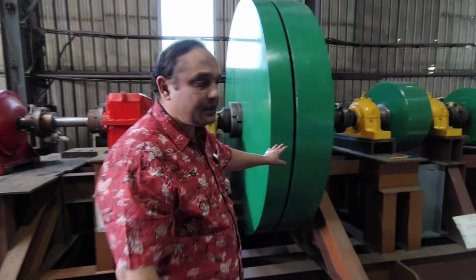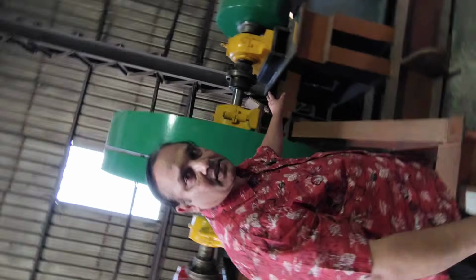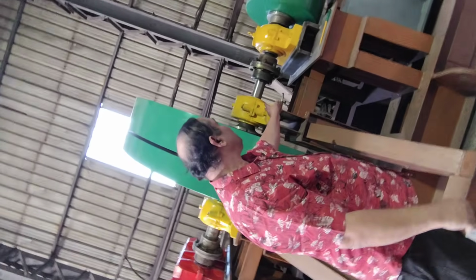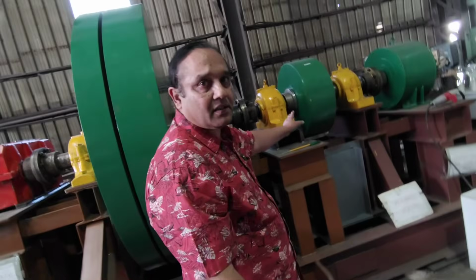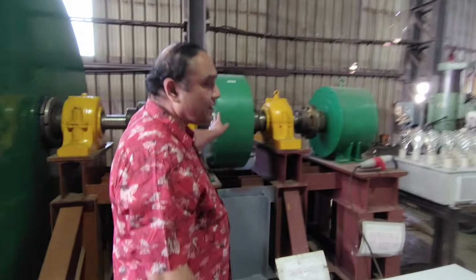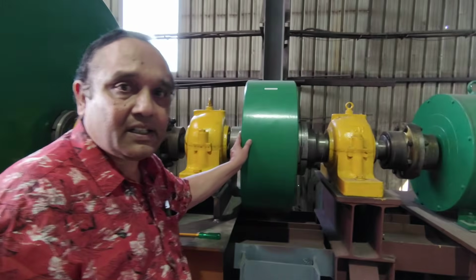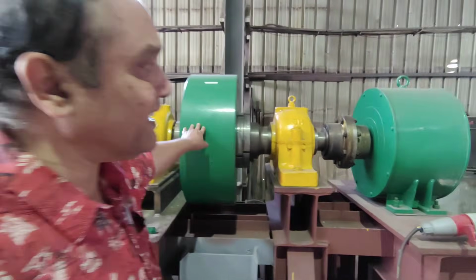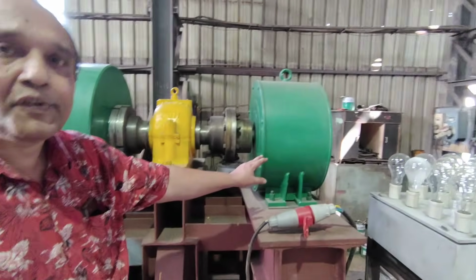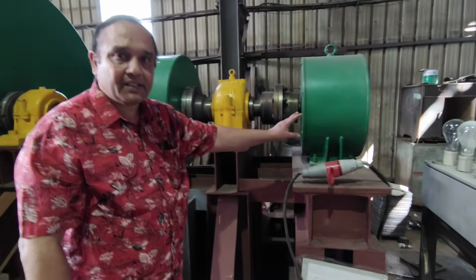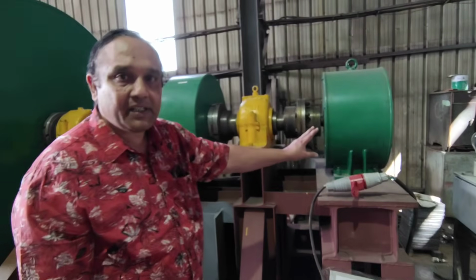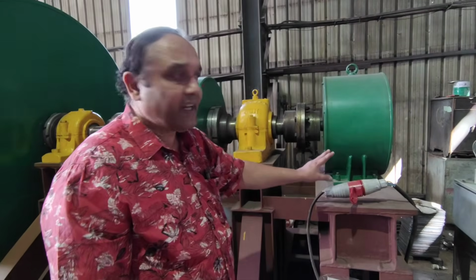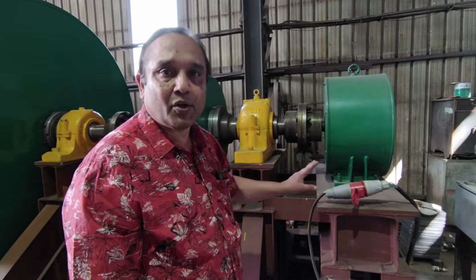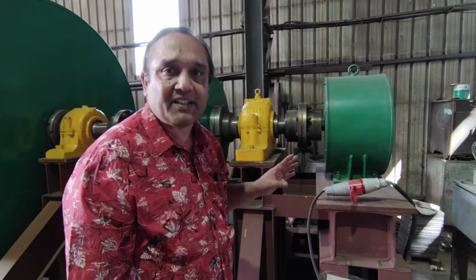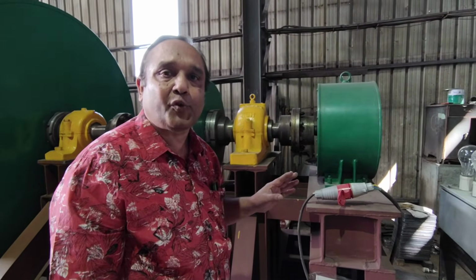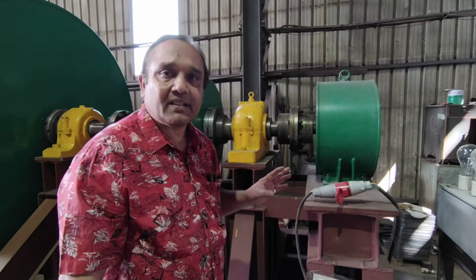Now we will be explaining the other parts of the skid. This is the guide wheel. The guide wheel is 1 ton, and it is connected to the generator, which is 15 kilowatt in capacity. This is a 24 pole PMG, permanent magnet generator, and this 24 pole is rotated at 250 RPM basic design structure, and it can go up to 400 rotations in this design.